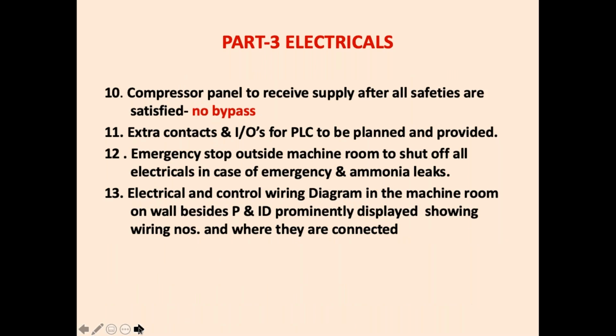Compressor panel to receive supply after all the safeties are satisfied. A very, very important issue. I will tell you a very big accident took place in Pune. I will not name the client, but what he had done, HP cutout constantly trips, so he bypassed the HP cutout, and the plant was operated with the result that big pressures built up in the system. There was no protection and the big accident took place. Such a big accident that even the building collapsed.